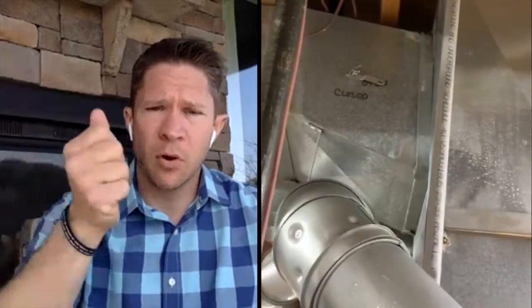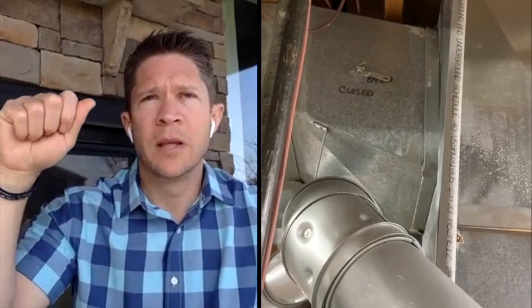And the dampers are usually located near your furnace? Yep. If you're looking at the furnace straight up, we call it a plenum. So it's just the big metal box that comes off the top of the furnace, and then it separates out throughout your home. Right where it starts to branch out is usually where they will install some manual dampers. I always told homeowners there's usually a handle to grab hold of to rotate that damper. The direction of that metal baffle or damper is also the direction of the handle, should be.